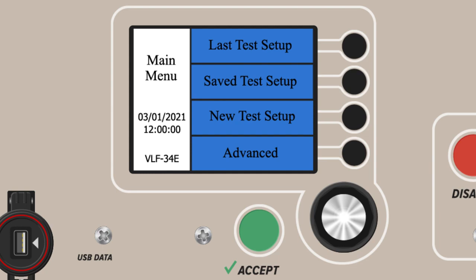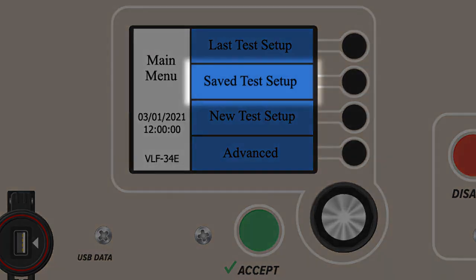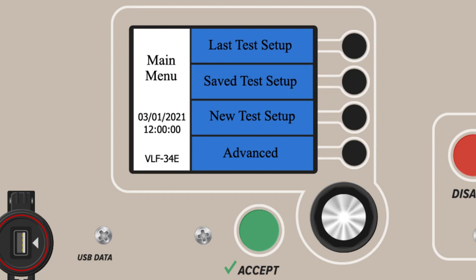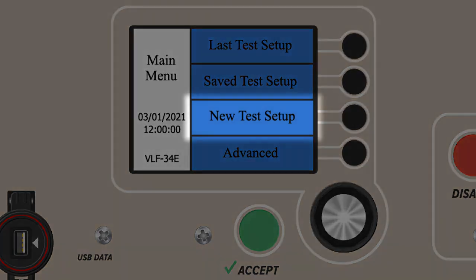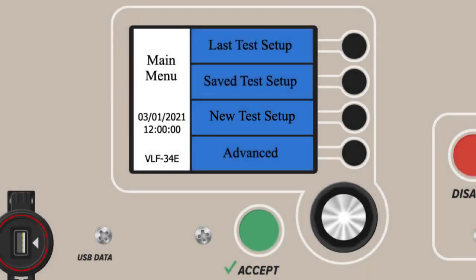The second option from the main menu is Saved Test Setup. This allows users to choose, view, or edit a predefined and saved test profile or sequence. Many test profiles can be stored and used again later. The third option from the main menu is New Test Setup. From here, users can operate from manual mode to run high-voltage tests on devices under test. Manual mode is the only mode that lets testing professionals adjust testing parameters after a test has begun.